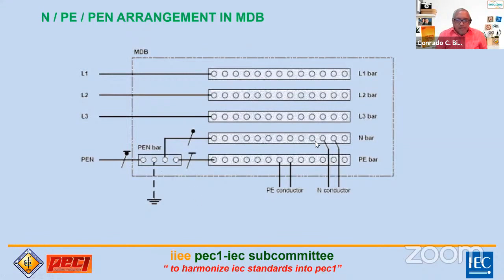So this is another PEN bar na pwede kang maglagay ng isang bar separately from these two. Makikita natin na may mga connections, sa PEN, nag-separate siya dito, then dito yung earthing niya, separate niya between the earth bar and the neutral bar. So all these connections are allowed as long as you respect how you use it. Kung PEN mo siyang PEN, you have to connect it the way it is. Yung PEN mo naka-earth, so pag separate mo, kung PE na, neutral na yung isa. Napakahalaga nitong connection na ito, itong earthing conductor na ito.